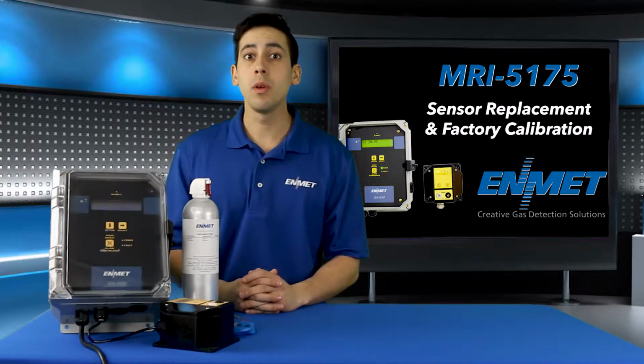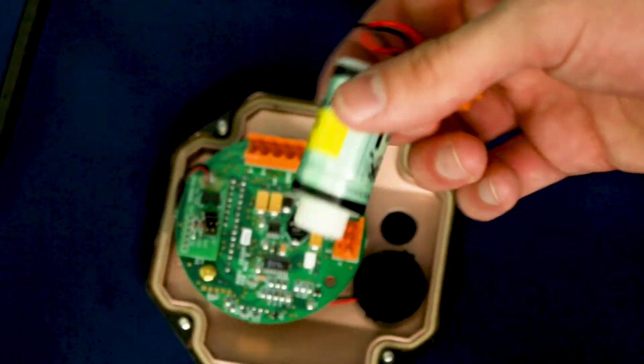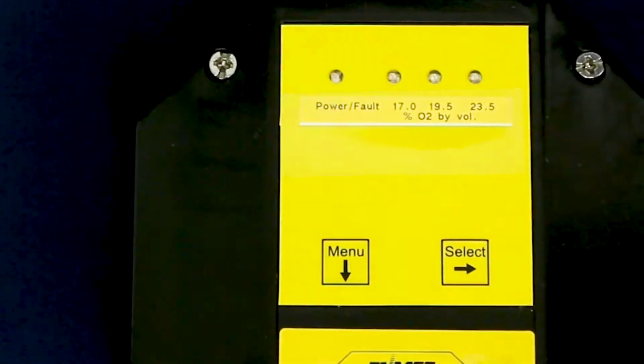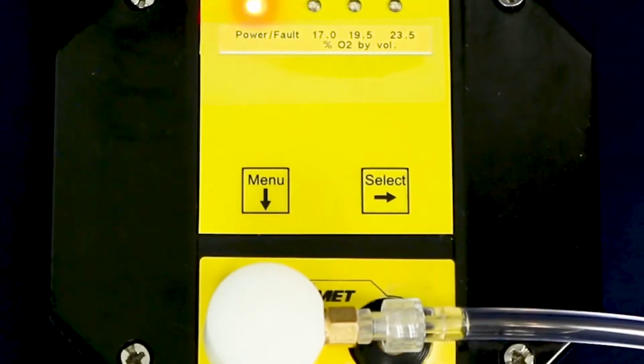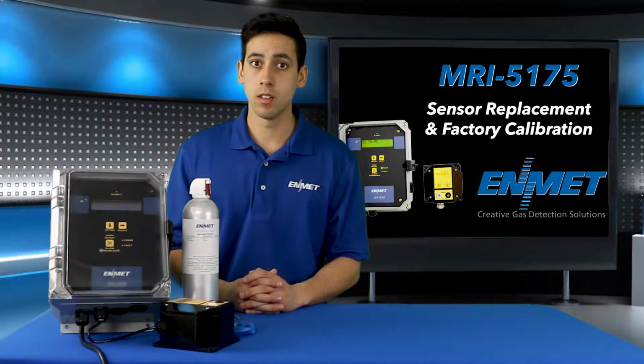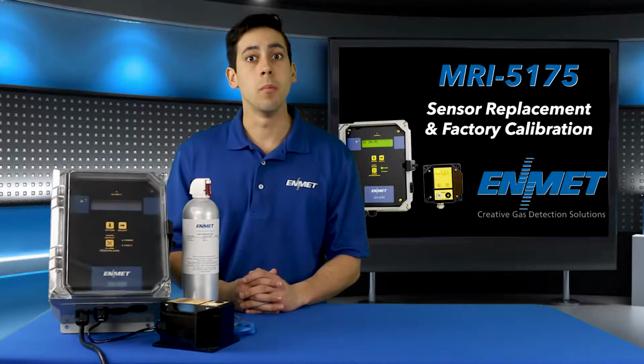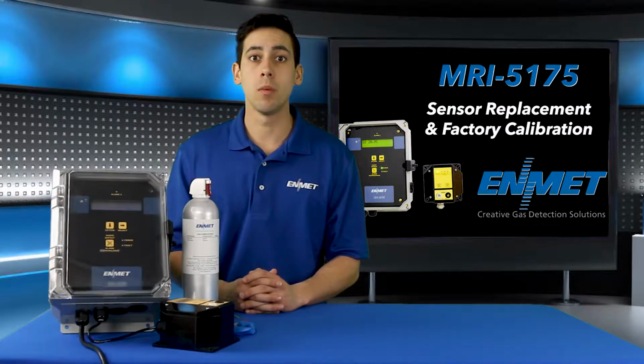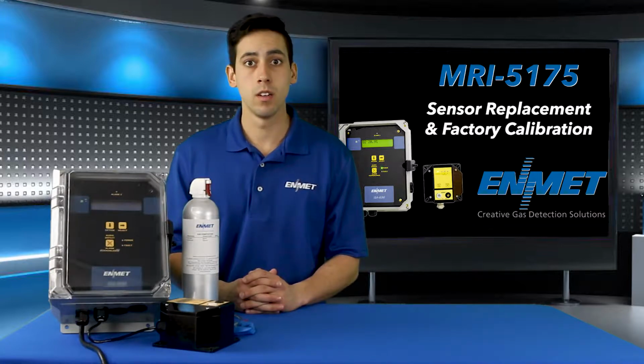In this video, I'll be walking you through how to replace the O2 sensor of ENMET's MRI 5175 and then perform a factory calibration after the sensor replacement. An oxygen sensor must be replaced when it can no longer be calibrated. The typical life of a sensor is 3 to 5 years in a 20.9% oxygen environment.